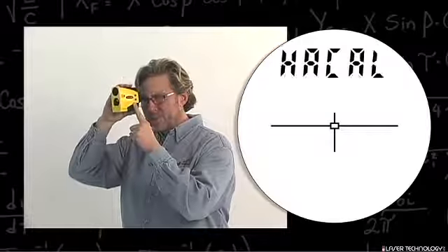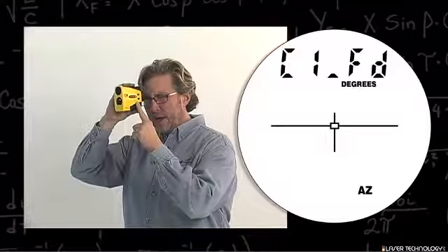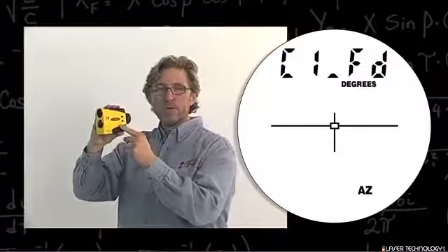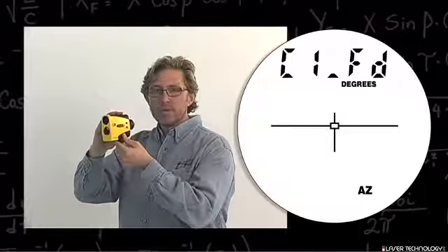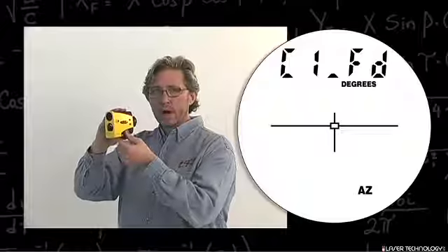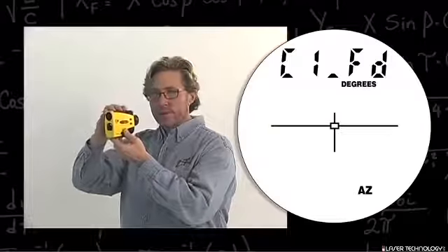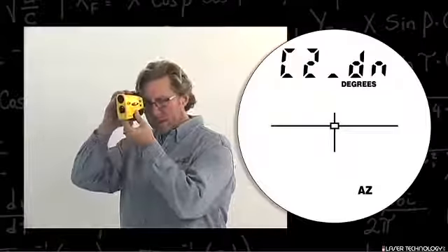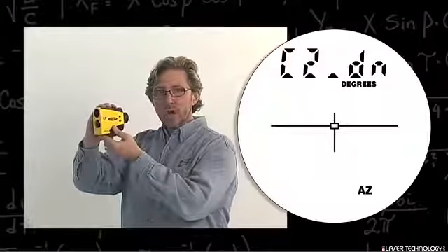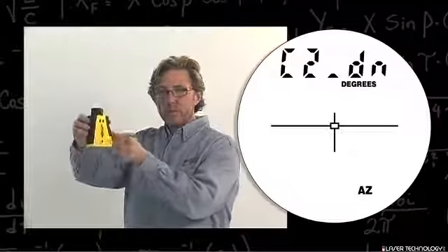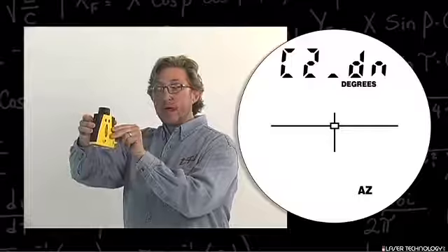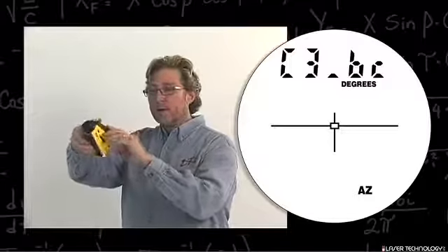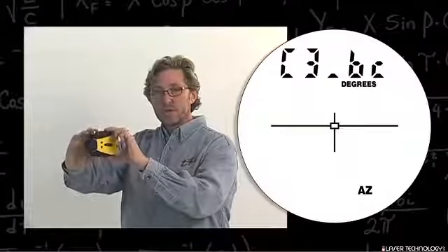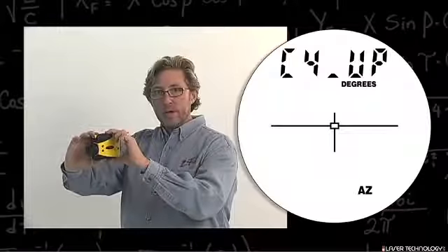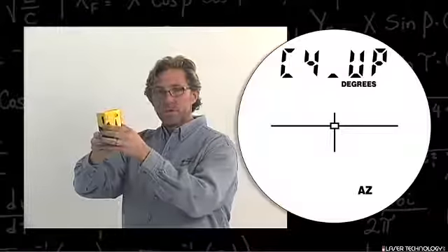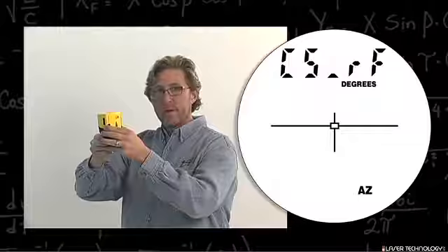At this point you hit the fire button and we will begin the calibration routine. When you look into the unit, it will say C1_FD. You hit the fire button, and if you look into the unit, it will say C2_down. This is where you point the unit straight to the ground and you hit the fire button. The next is you turn it back toward yourself and hit the fire button. We point the unit straight up and hit the fire button.